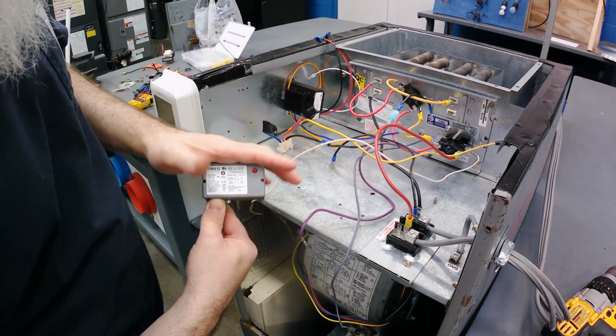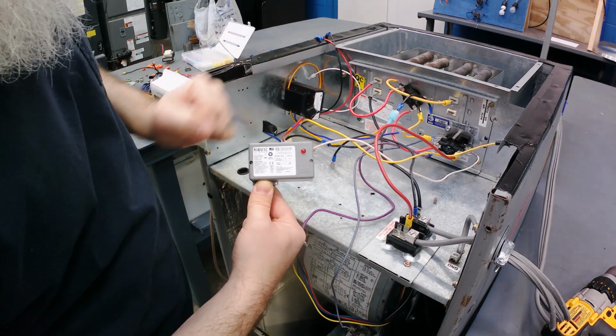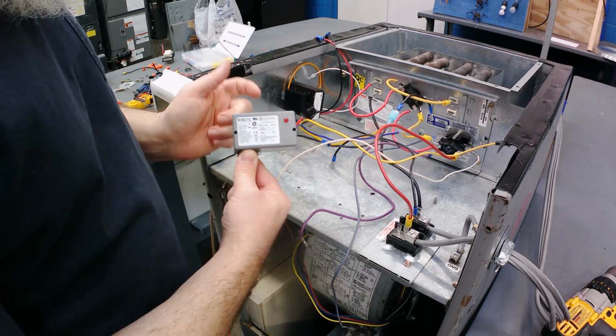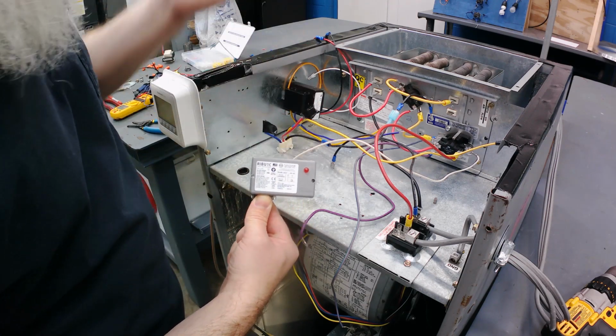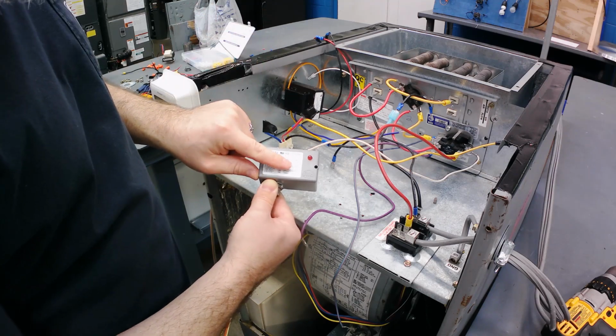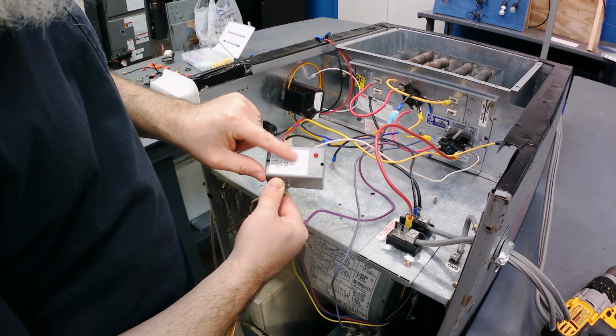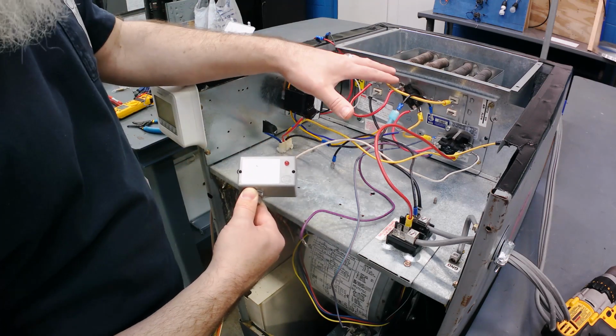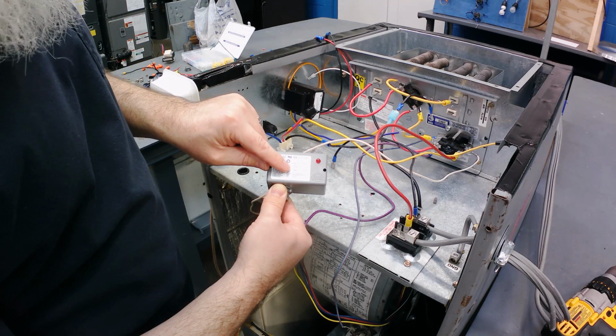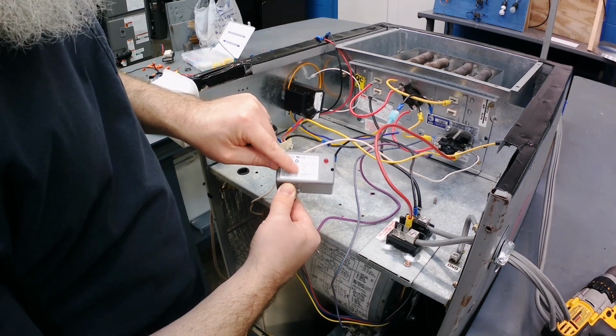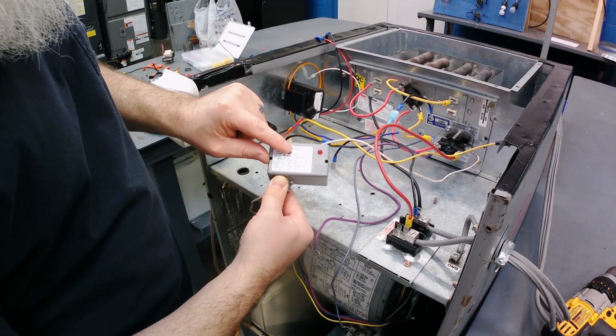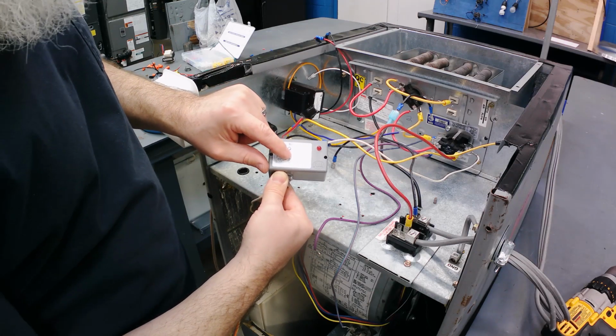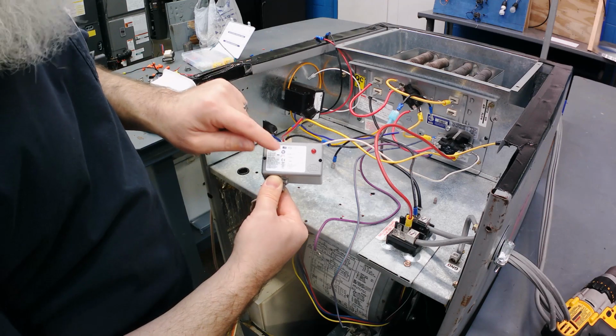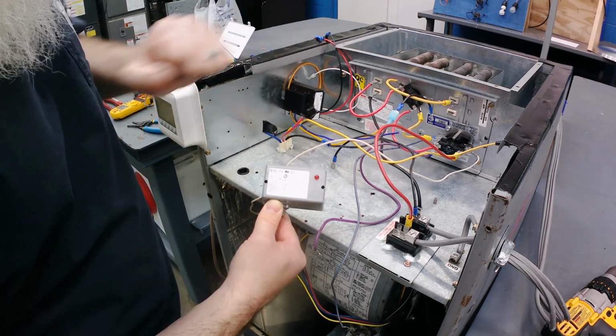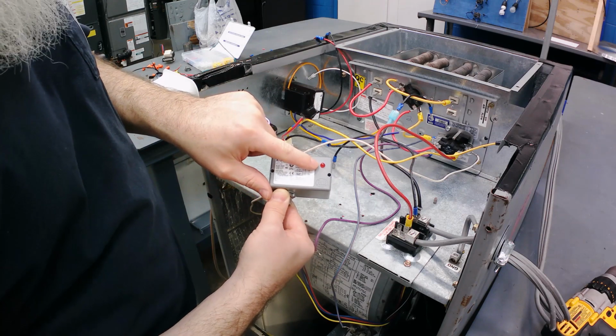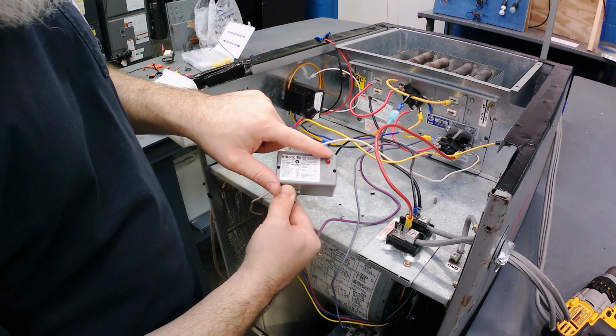We're using this in place of a regular 90-340 relay. This one's maybe a little more light commercial, so it's just a different look, but it's still just a relay. If you look at the picture on the front, they show you the common, normally open, and normally closed switches, which we already had in this system, and they even show you which wires to use for your coil voltage. This one has a 120 volt coil or a 10 to 30 volt AC or DC coil, so we'll use that one since we have a 24 volt system, and it should work out pretty well. It's even got a little red LED to tell us when the coil is getting power.